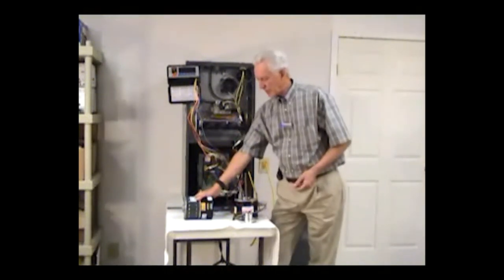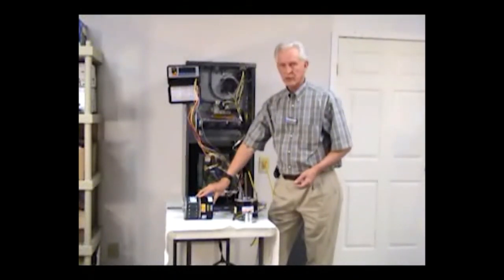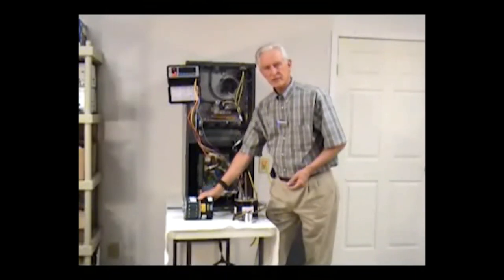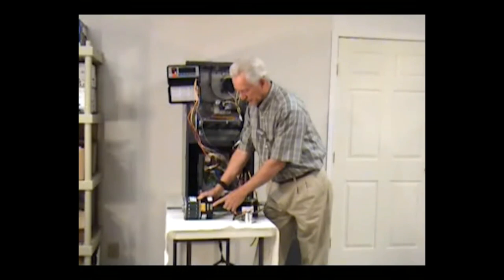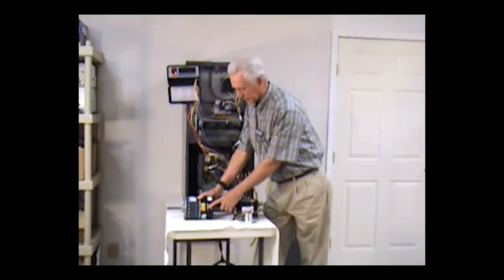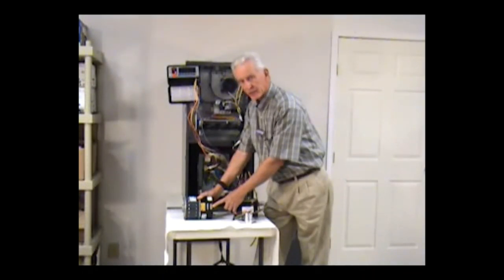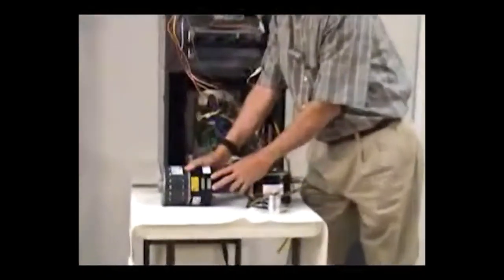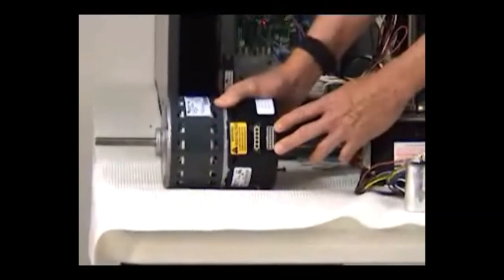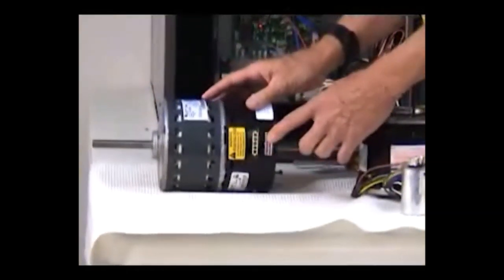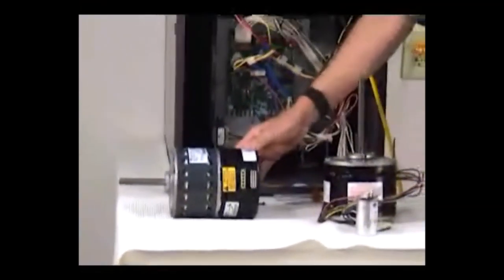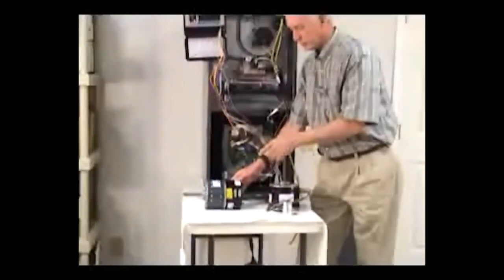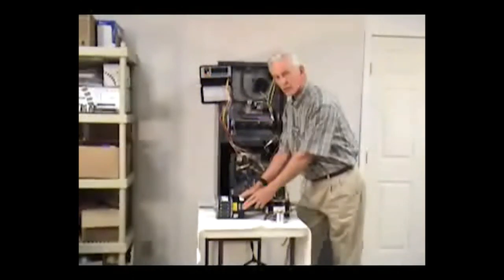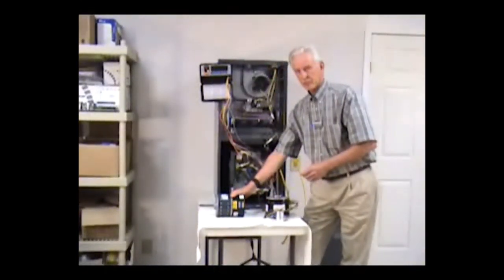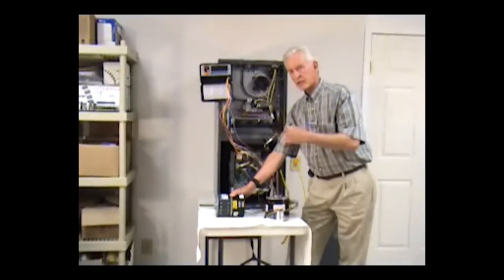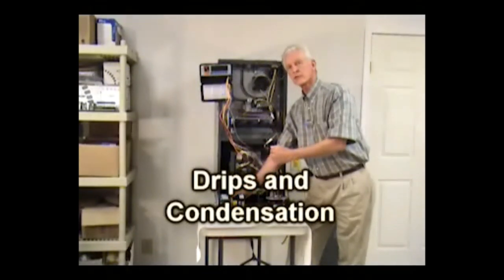Okay, and the last one has been introduced in the early part of 2007. Looks very much the same still, except with a couple of changes that they have made. We still have line voltage and maybe a larger connector here, but we no longer have a 16-pin connector at this point. We have a 4-pin connector only in a large configuration as well, but still looks very much the same with those two connectors on it. In that particular case, our thermostat is communicating with the board, though, and then the board in turn communicates through the 4-wire connector. It goes to the module on the motor itself. And that is pretty much the extent of the difference between the earliest models of these all the way through until the current ones that are now coming out.